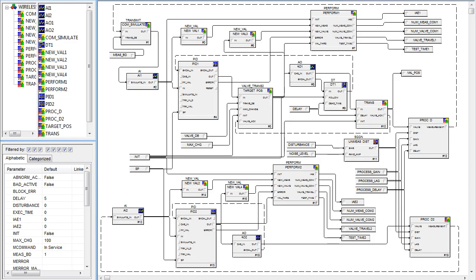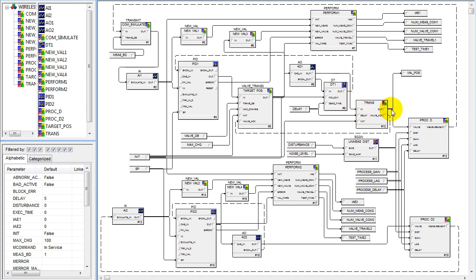This is our module that we'll be using in the workshop. In the upper portion is the wireless control. We're simulating our wireless transmitter. PID Plus is being used — the PID has the PID Plus option enabled. We're simulating the delay, and there's an added component between the PID Plus and the AO to handle the fact that we only allow action to be taken after we've received acknowledgement of the last output. The time to apply command is being simulated and is used in adjusting our wireless throttling valve.